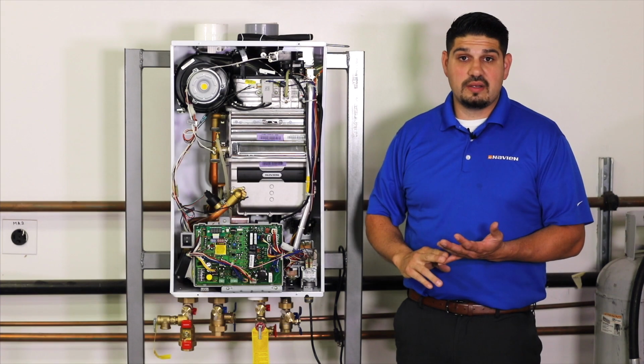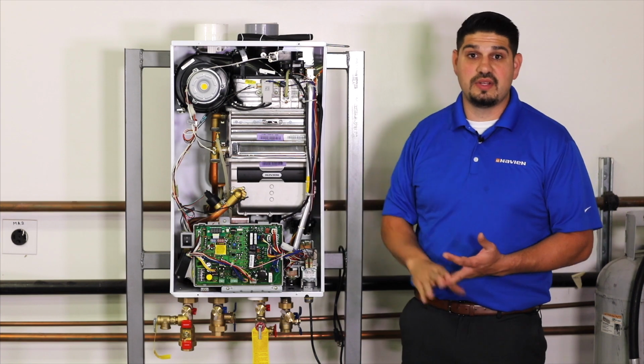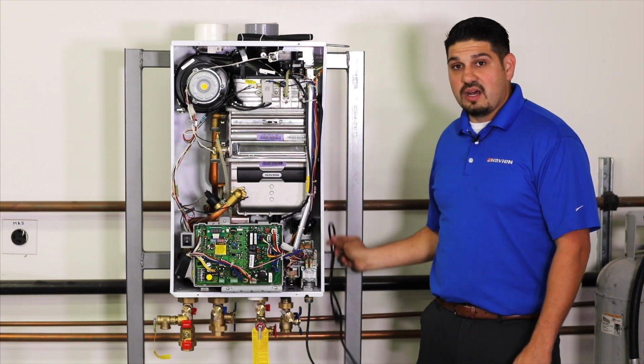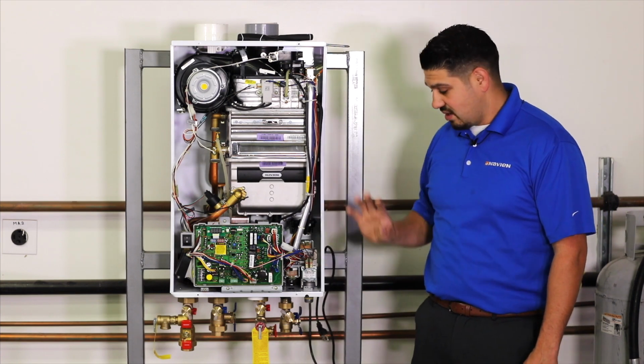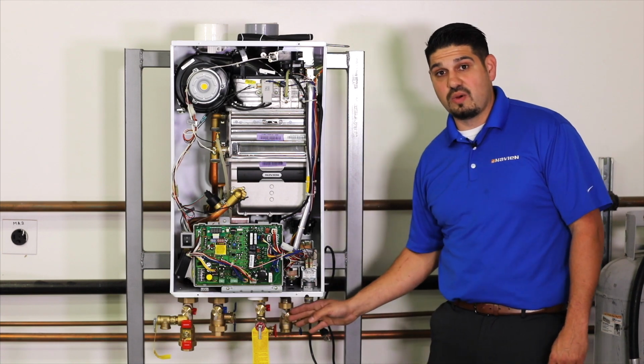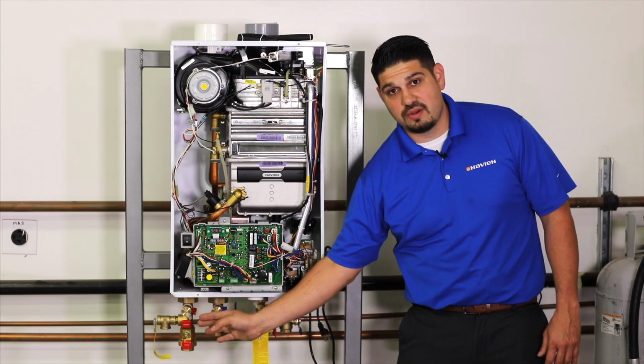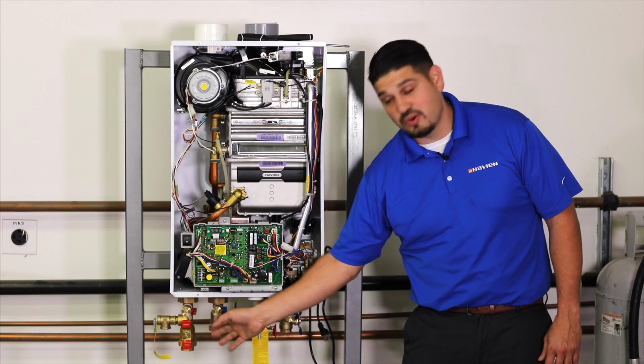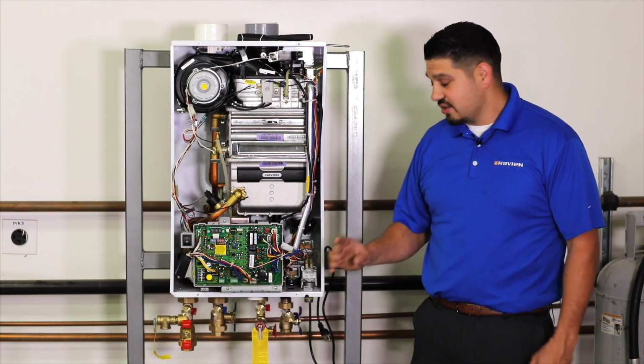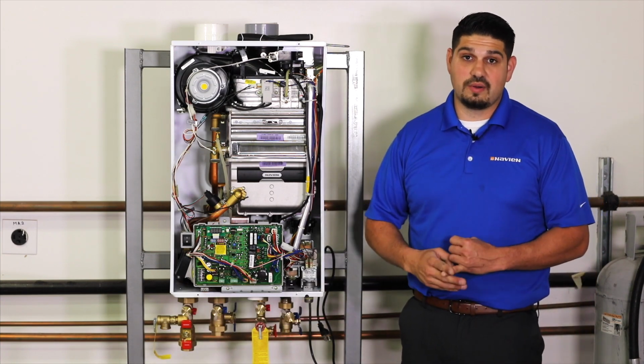Before we get started on replacing these heat exchangers, some things you want to make sure to do. Go ahead and unplug your combi. You're going to shut down your domestic water coming in and close off your heating water coming out, and both hot and cold on each side. Also, be sure to go ahead and close off your gas line.